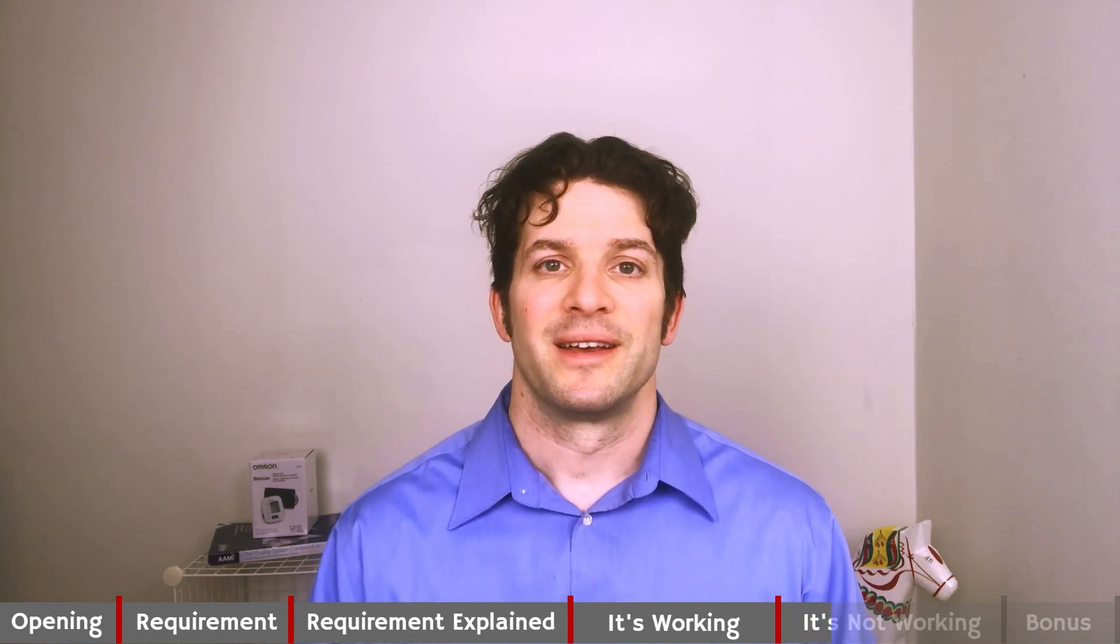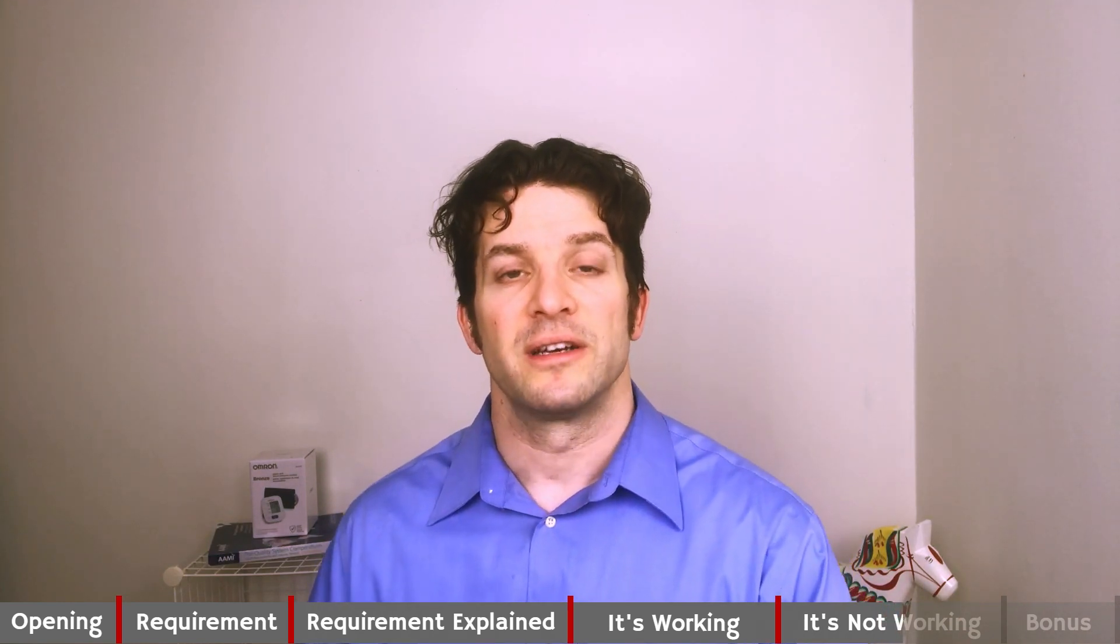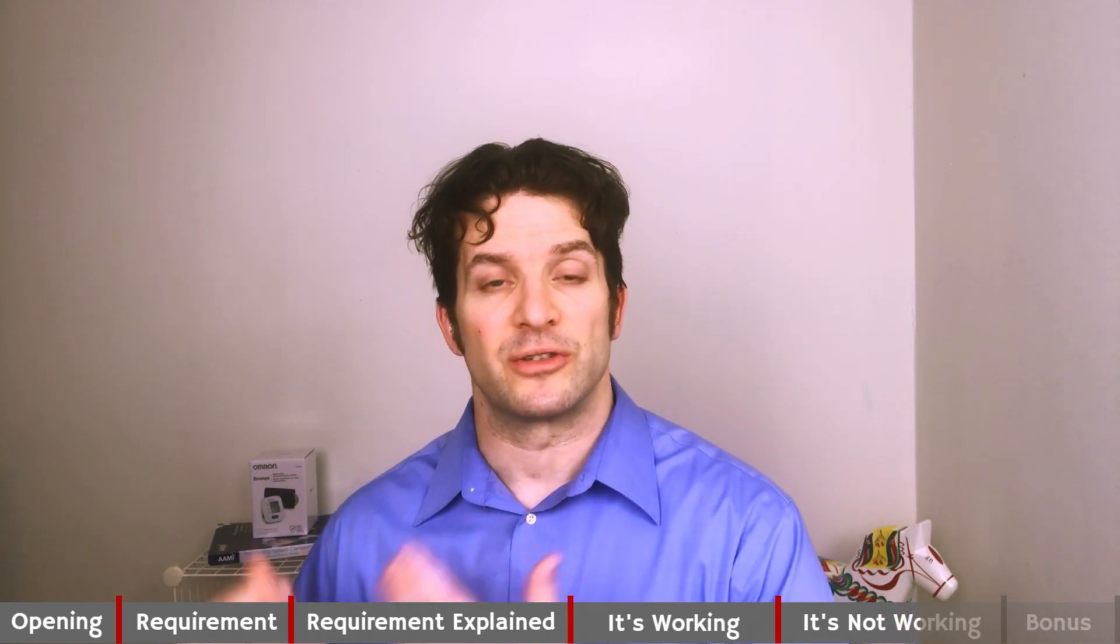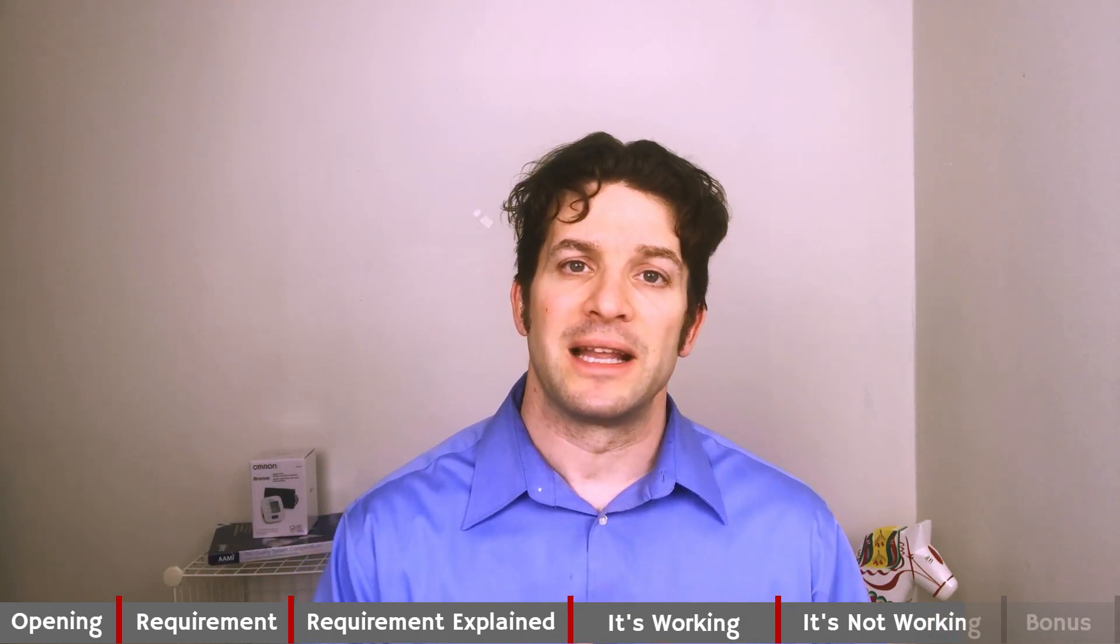So how do I know it's not working? Well, first, I'm not keeping copies of the labels in the DHR. Second, my labels get mixed up, I'm not reconciling labels, and the wrong label gets put on a product, and that product is released. So I have a recall due to label mix-ups. And then finally, my labels do not maintain their integrity, so they fall off or they become illegible.